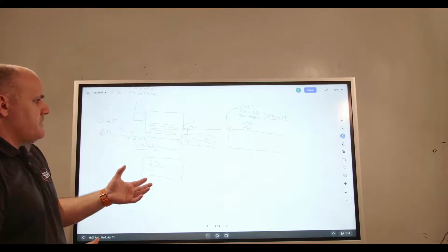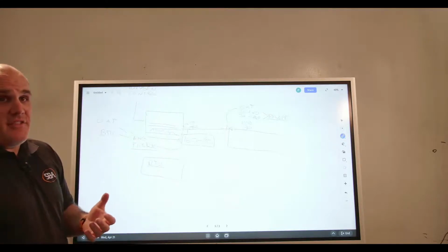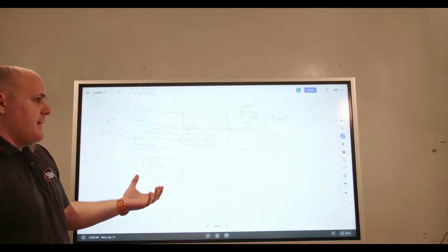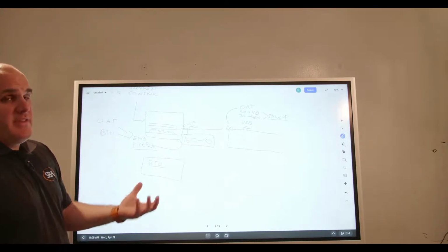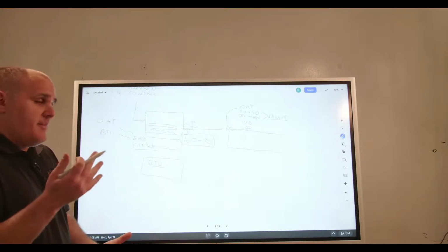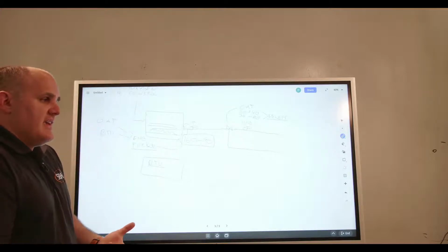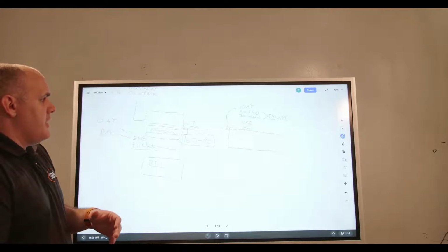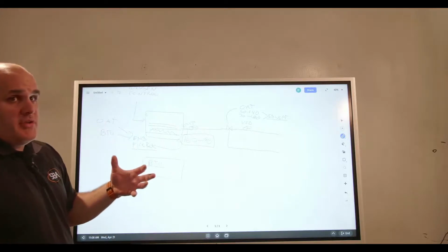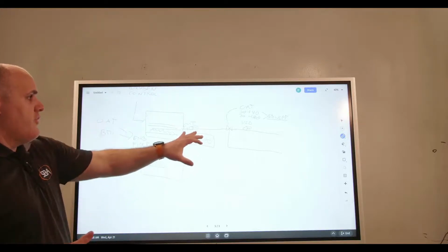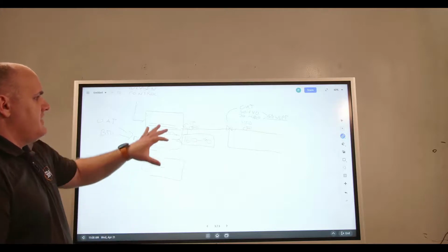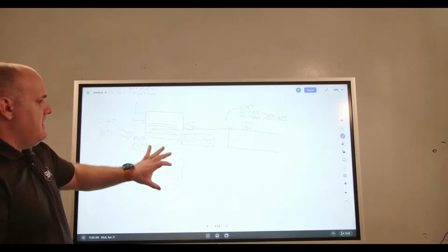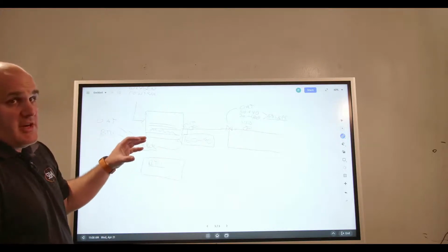But oftentimes you'll have boilers that are added after the fact and they don't have the same burner capacity, so they don't have the same BTU capacity, they don't heat up as quickly, or they heat up more quickly. And so then you come into a scenario where you don't want to run them in unison because you can actually end up overshooting. So what I will tend to do is run a boiler to max and then bring on a secondary boiler as required.